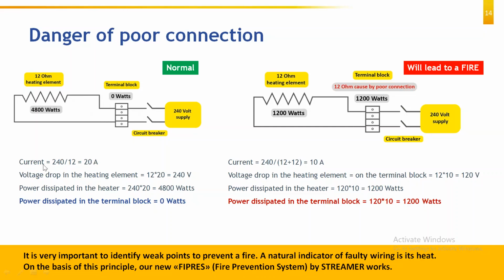That is why the total current flowing in this loop will be 240 divided by 12, the total loop resistance. So the current flowing through this loop will be around 20 ampere. The voltage drop across the heating element will be 20 amperes multiplied by the resistance of the heater, which is approximately 240 volts. It is obvious that because there is nothing else in the circuit, the whole voltage will drop across the heating element itself. So power dissipated in the heater will be 240 into 20 ampere, that is, power equals current into voltage. The power dissipated will be 4800 watts. The power dissipated in the terminal block will be 0 watt. Similarly, the power dissipated in the contact of the circuit breaker will be 0 watt.